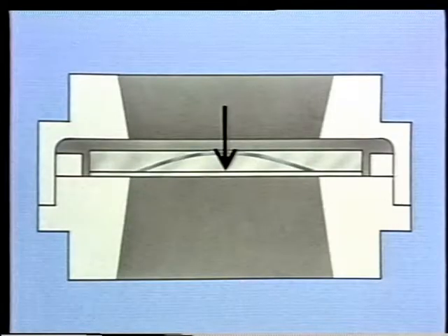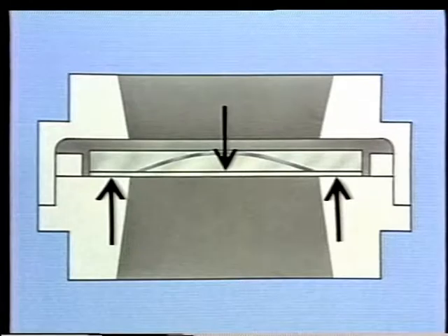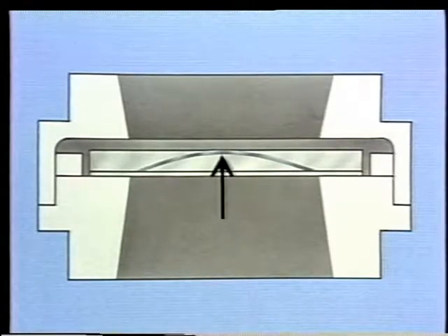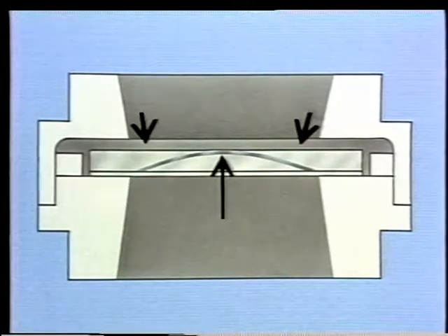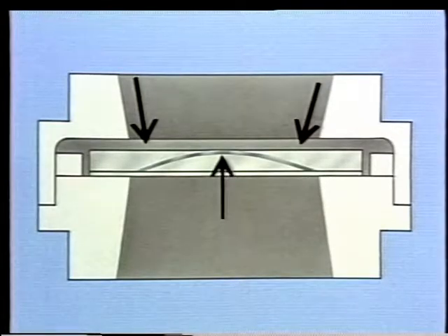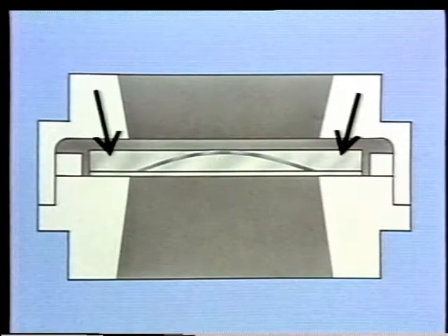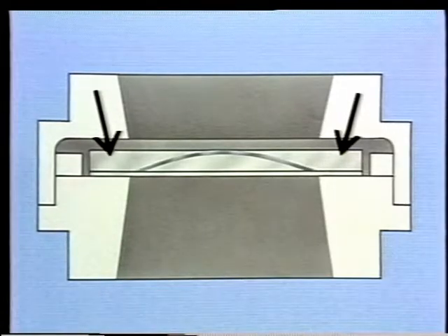The channel in a channel valve acts like the feathers or valve plates in other valves. The channel sits on the valve seat and blocks the air path between the inlet and the outlet. A leaf spring holds the channel against the valve seat. The stop plate has raised areas that hold the leaf spring against the channel. The channel guide holds the channels and directs its up and down motion.